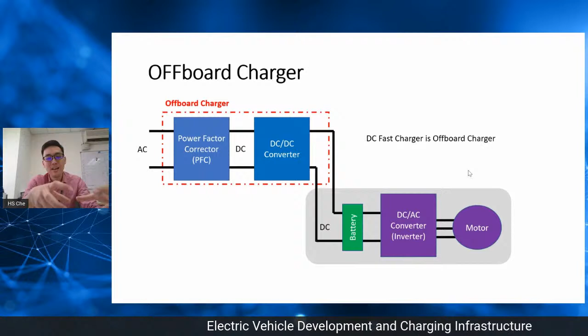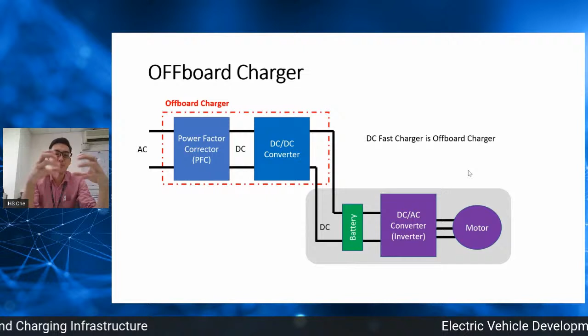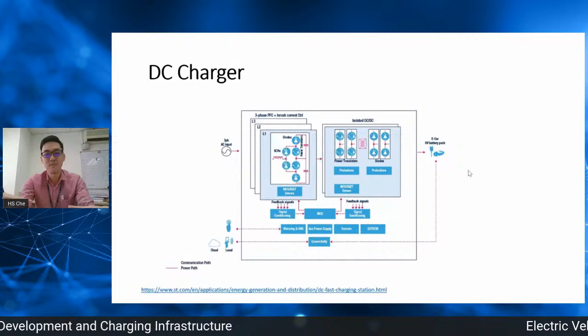What is done in DC fast chargers is that instead of relying on the charger onboard, we take out the power factor correctors and DC converter and put them outside, so we can make the size much, much bigger. The power can go from 7 kilowatts to hundreds of kilowatts. This is usually done using multiple modules - one module, say 50 kilowatts, or maybe 5 modules of 10 kilowatt DC converters, then you can achieve the power.